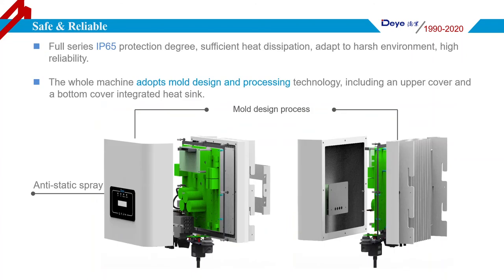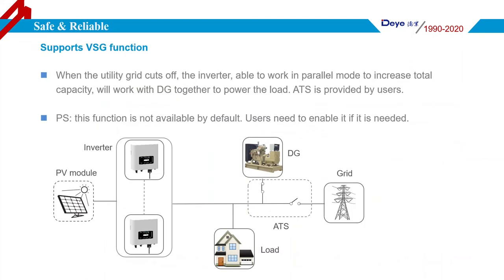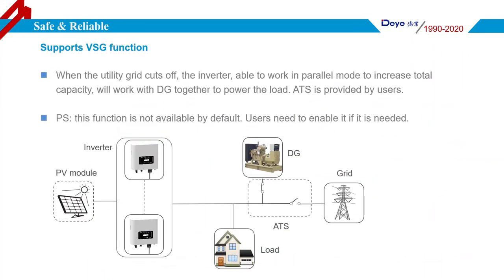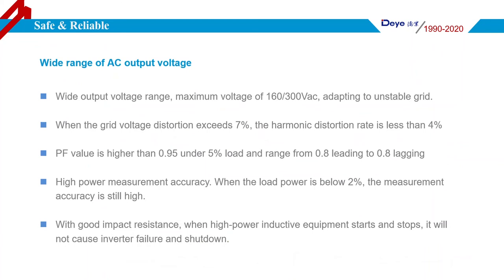The whole series of string inverters has IP65 protection, and the whole machine adopts a corrosion-resistant design, ensuring the inverter can adapt to harsh environments. A core feature is the VSG function: in poor-grid or off-grid areas, string inverters can work with a diesel generator without an additional EMS device. Other features include a wide output voltage range of 160 to 300V, and when grid voltage distortion exceeds 7%, the harmonic distortion rate can still be kept below 4%.